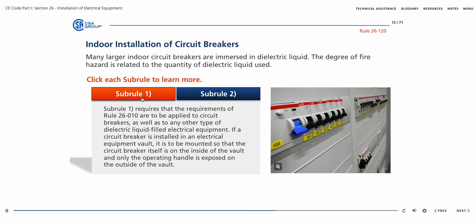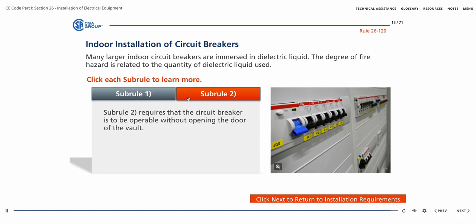If a circuit breaker is installed in an electrical equipment vault, it is to be mounted so that the circuit breaker itself is on the inside of the vault, and only the operating handle is exposed on the outside of the vault. Sub-Rule 2 requires that the circuit breaker is to be operable without opening the door of the vault.